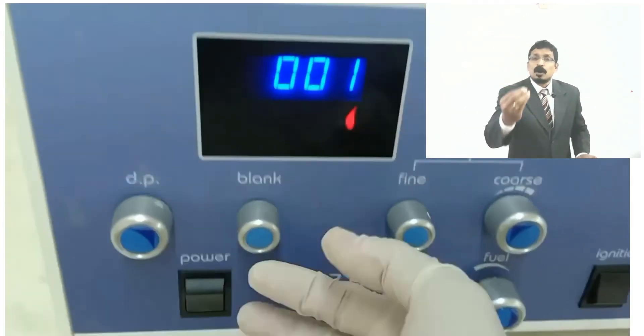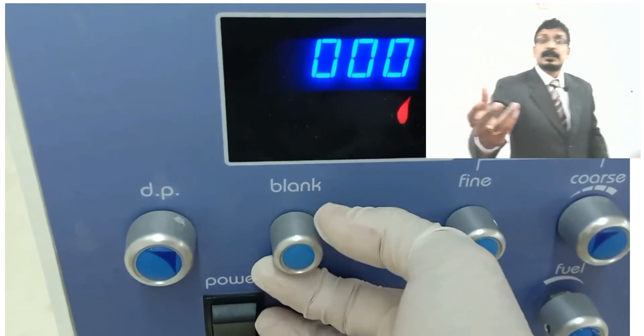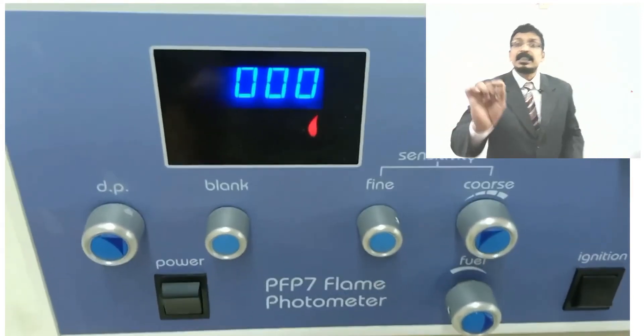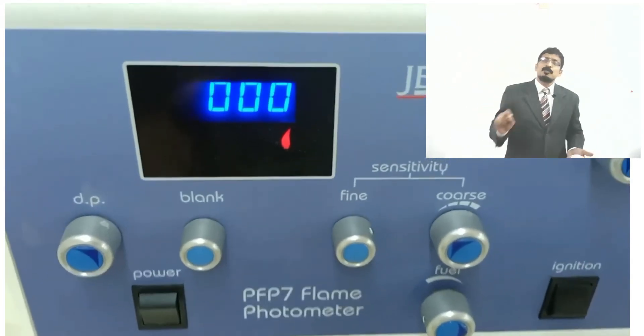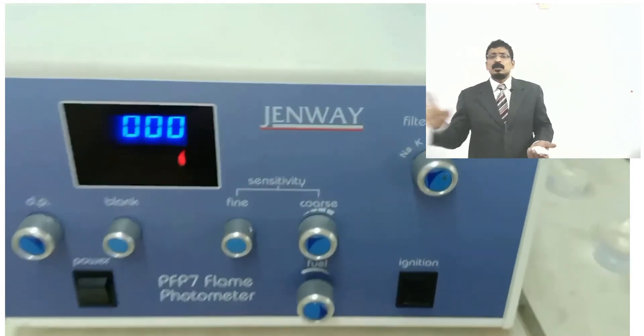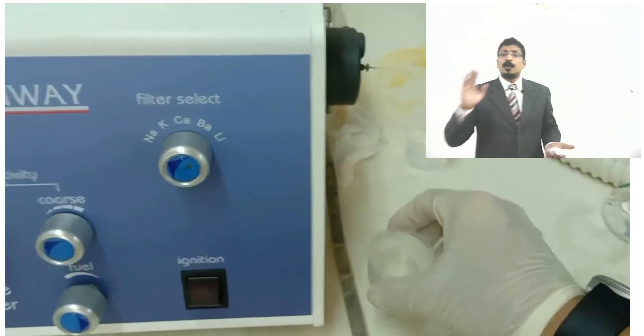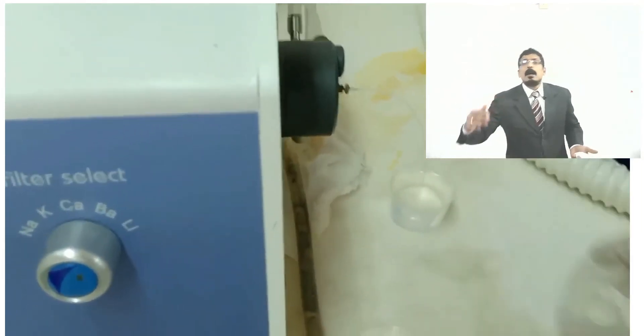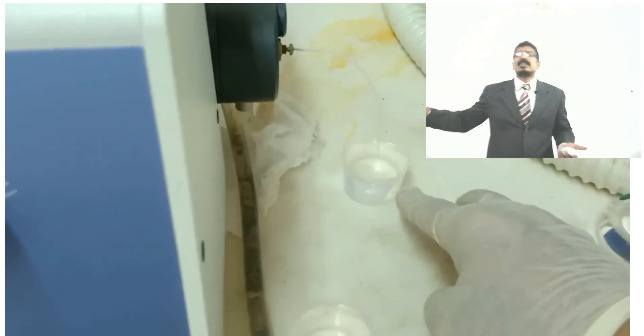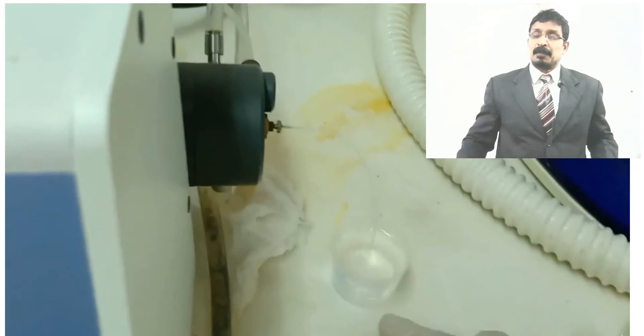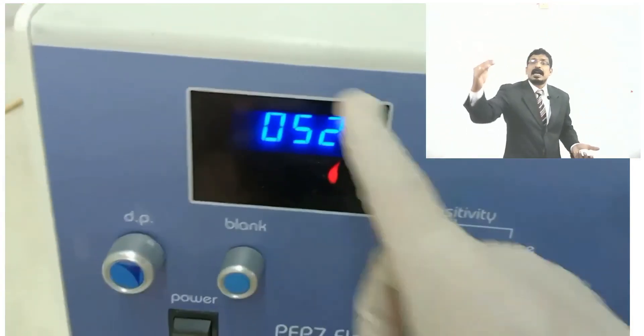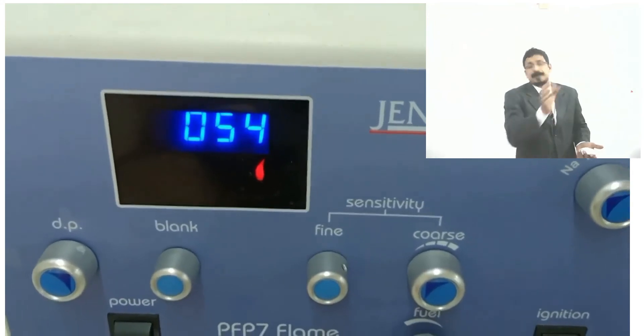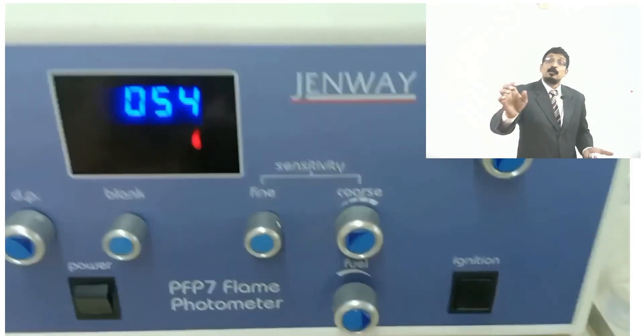Set zero with distilled water and take the highest concentration — adjust it to give a reading of 100. Then all other concentrations can be easily identified to make a standard graph. For the unknown sample, keep it in the same capillary tube, get a reading, and extrapolate from the y-axis to the x-axis on the graph to find the concentration. A simple graphical standard curve method is used for finding the concentration.